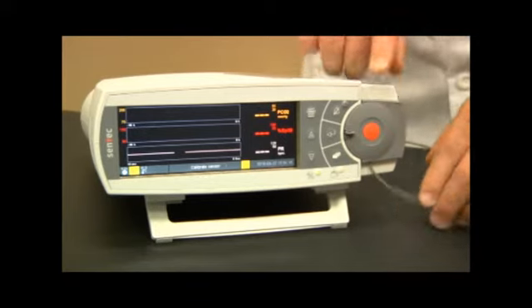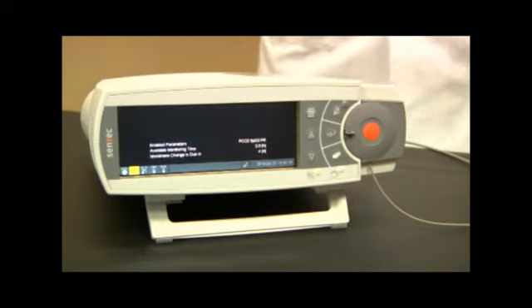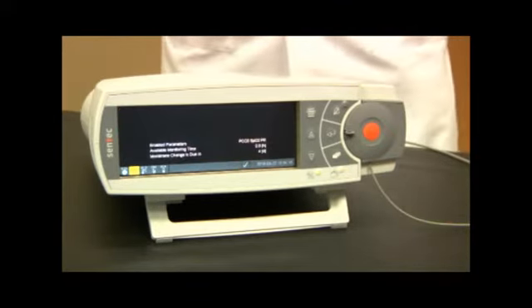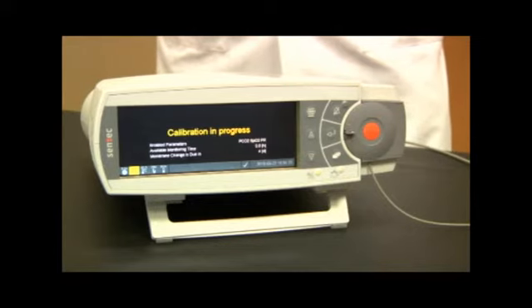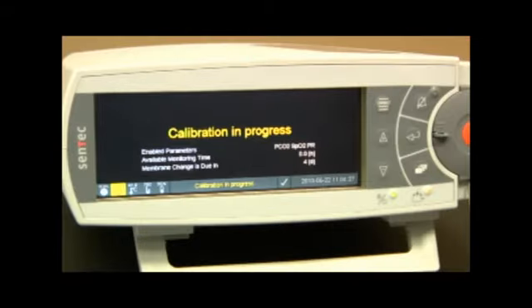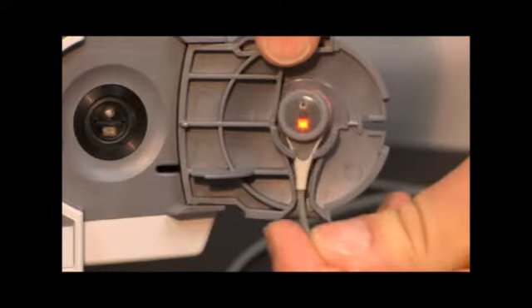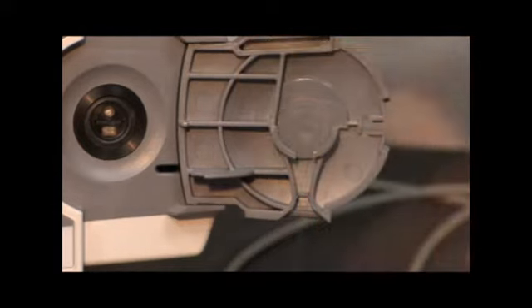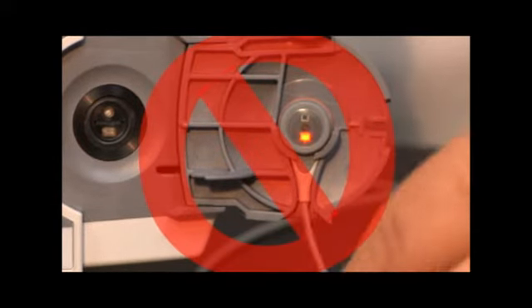Close the door, and when the sensor reaches the set temperature, the message "Calibration in progress" will appear. Under normal circumstances, the calibration should be accomplished in 3 to 5 minutes. If a calibration goes beyond 11 minutes, please check the sensor membrane status and/or the condition of the docking station. Remove the sensor by lifting up from the strain relief. Never pull the sensor from the carriage, as this may cause damage to the sensor cable and housing.